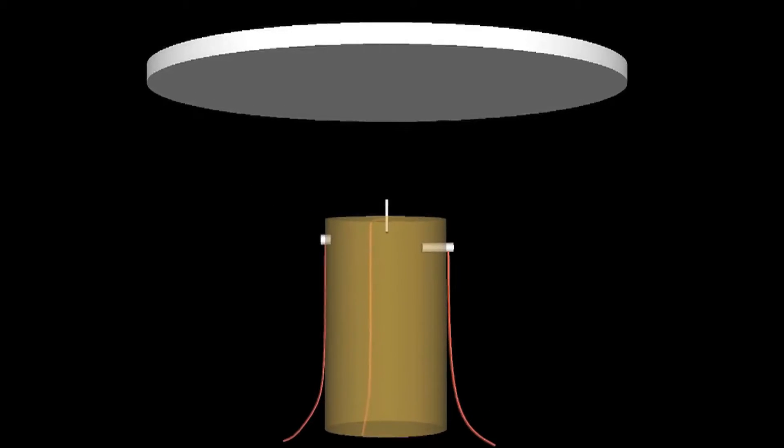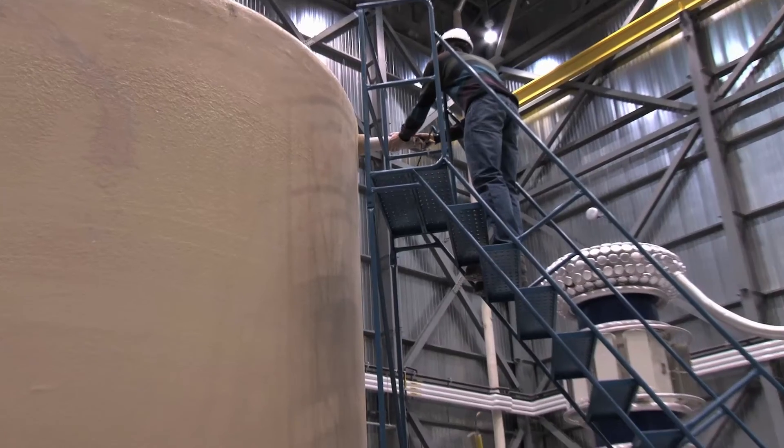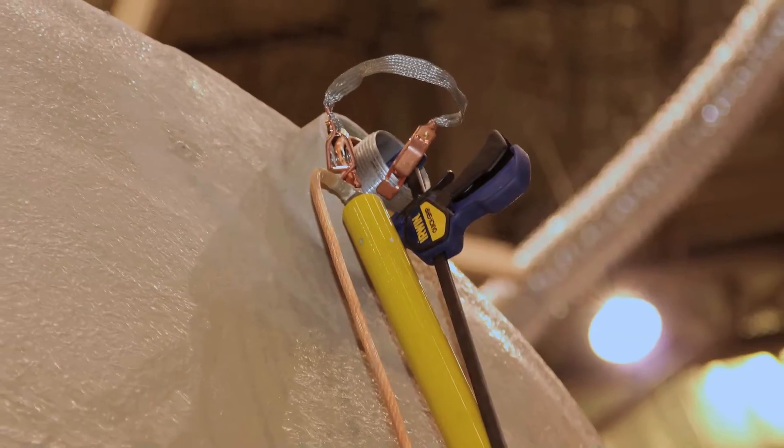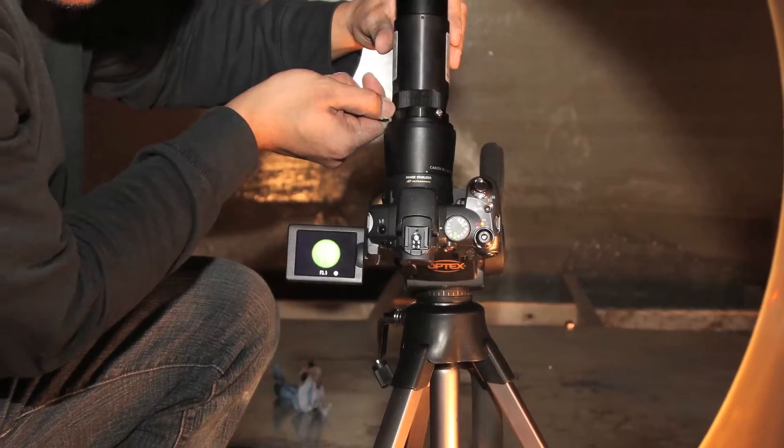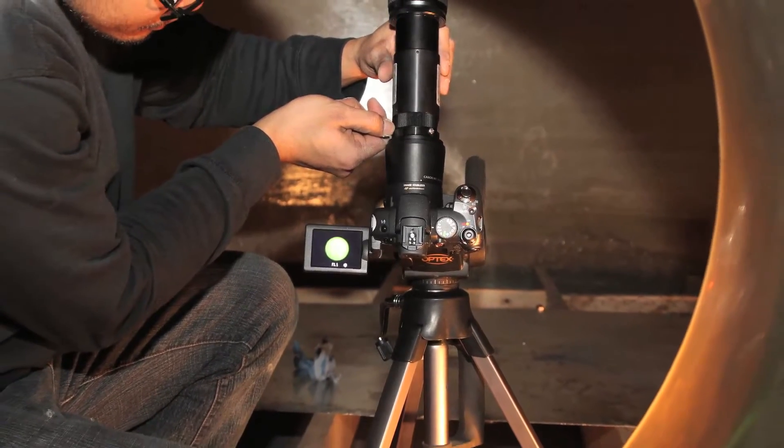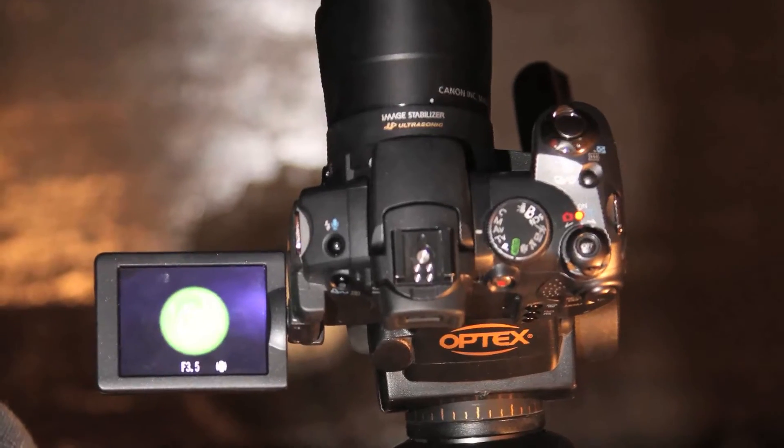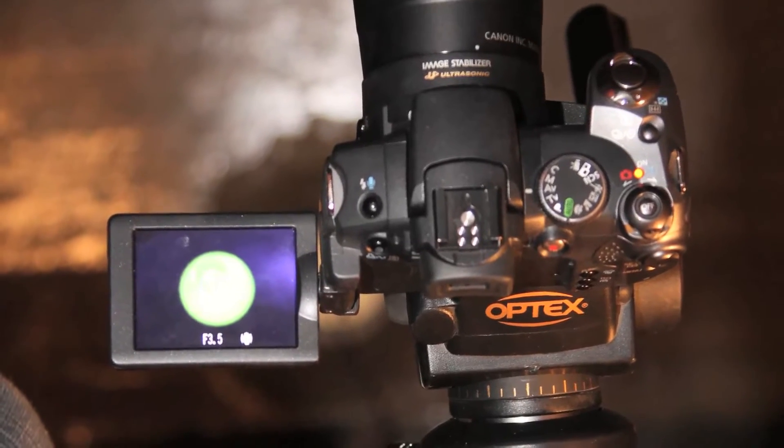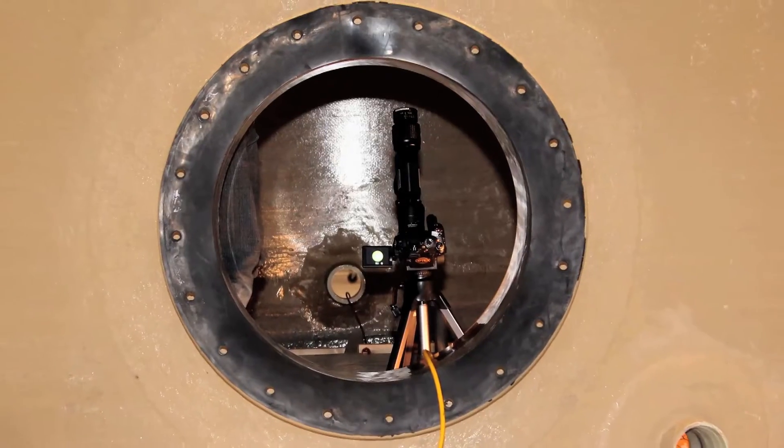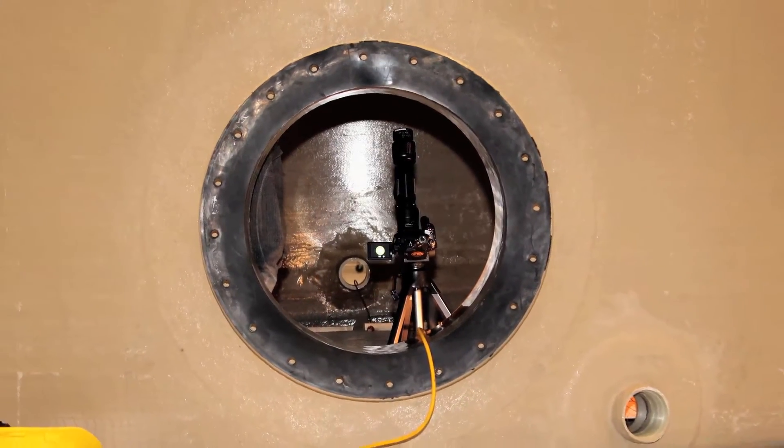Metallic pipes of varying lengths and diameters are inserted into the 5 meter high tank and grounded as per applicable standards. A coronascope or UV camera which is particularly sensitive to the wavelengths produced by sparks or streamer discharges is placed inside the tank and used to monitor for hazardous sparking.